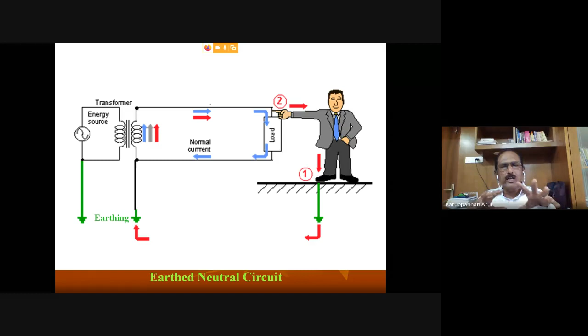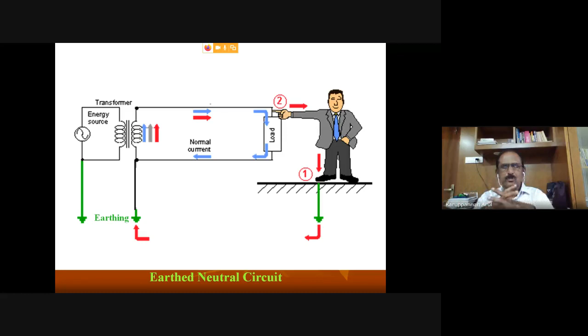Wherever we go, we should ensure the equipment has proper earthing, and the earthing should be tested so it does not exceed 5 ohms, ideally not more than 2 ohms. If the resistance is around 5 ohms, most of the current passing through the body of the equipment will go through the earth circuit. If you touch it, only a minimum amount will pass through our body, and since our resistance is more, we will be protected from electric shock. Earthing is a very good phenomena. In our grinder, mixer, or other household equipment, the ground wire acts as part of the earth. All ground wires are connected and earthed properly, so we won't get any electric shock from these household items. That is the importance of earthing.